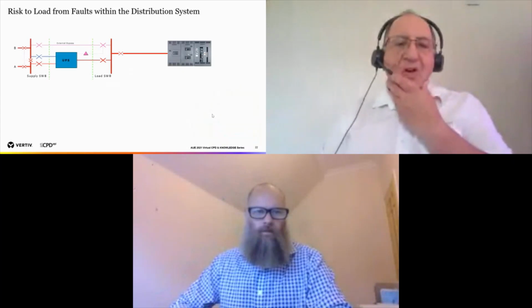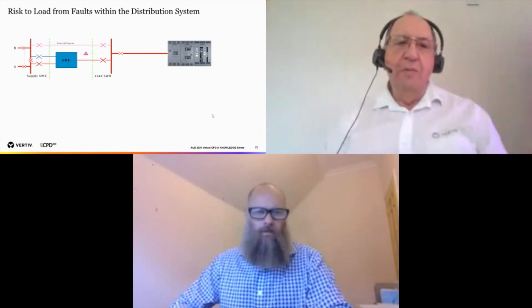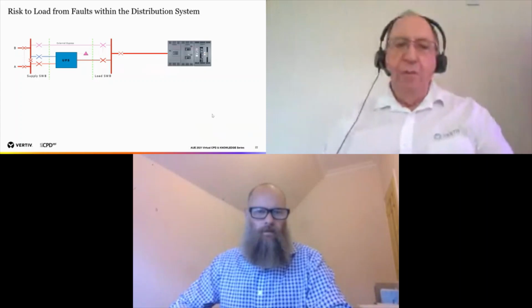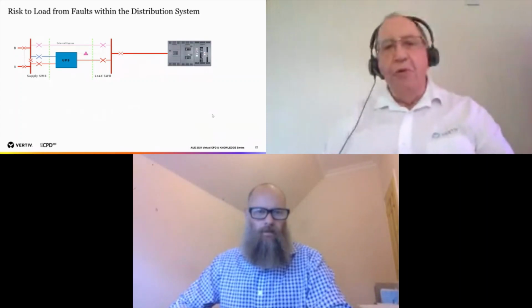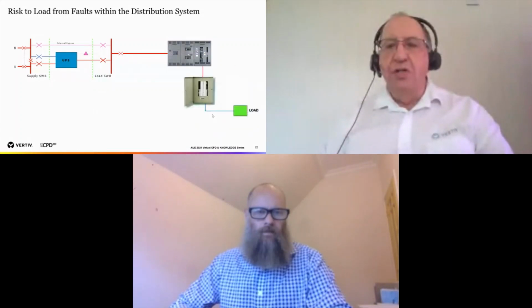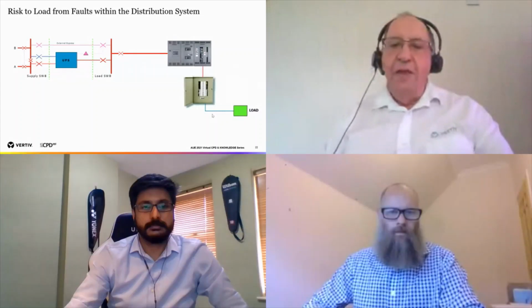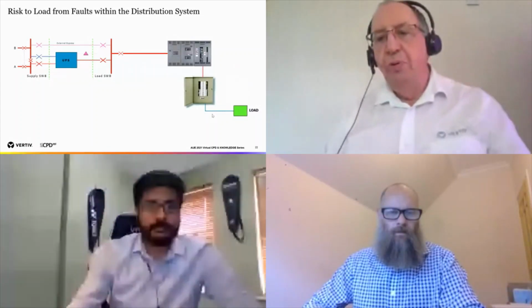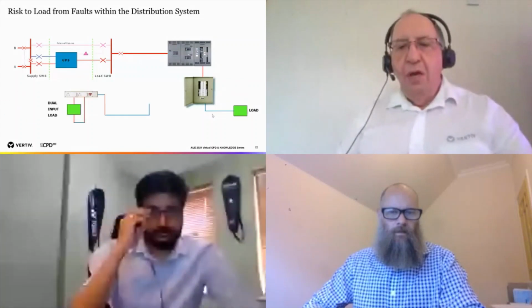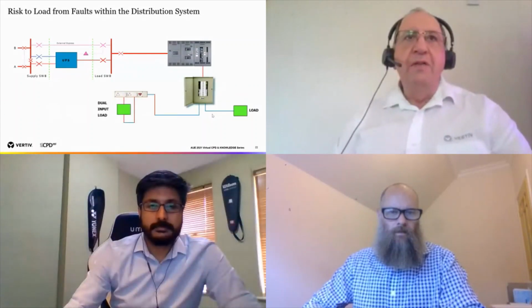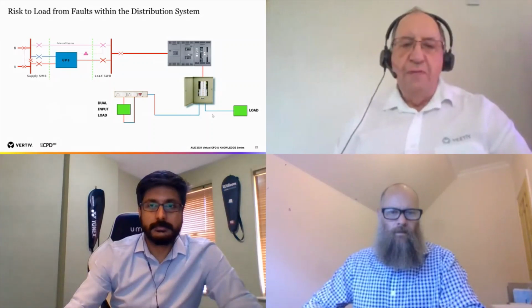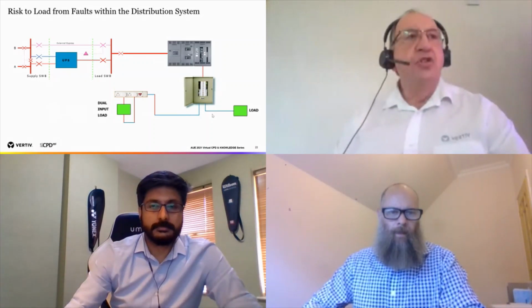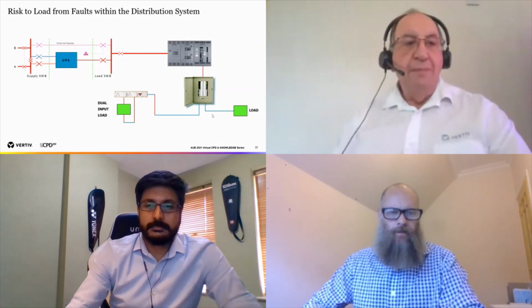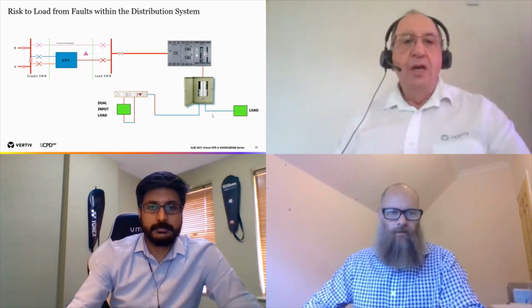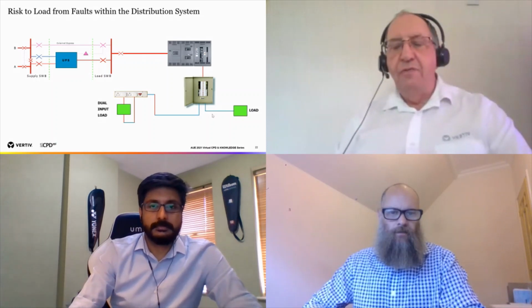So here we've got a UPS with a dual power supply coming into it. We have an external bypass and we have an output onto a switchboard, which is the SWB. And then downstream, we've got a circuit board. And then below that, we've got a distribution board with a critical load on. And it could well be that if we're talking about IT space or server space, that load has a dual input. So that means it's got an A and a B input, hopefully from different UPSs and different sources.